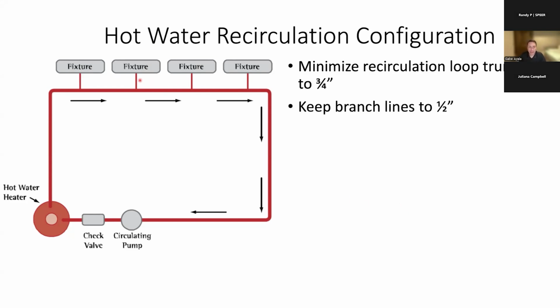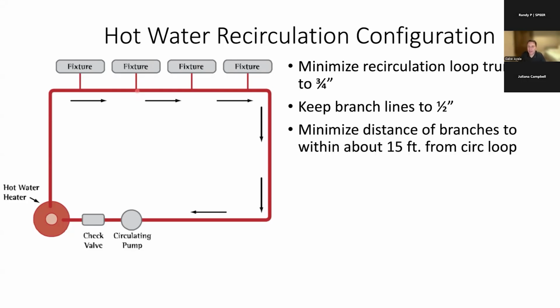And then if you keep the branch lines, the lines that are coming off of the main trunk line that go to each fixture, to about 1/2 inch and minimize the distance of the branch to about 15 feet, that's about 3 cups of water. So if you prime the loop with an on-demand system, then you're never going to wait for more than about 3 cups of water waiting for hot water at any fixture in the house. Obviously, all the trunk lines should be insulated. I think this is an energy code requirement. Even adding just minimal R4 pipe insulation considerably slows the cool down of those pipes. So it's very important that these be insulated.